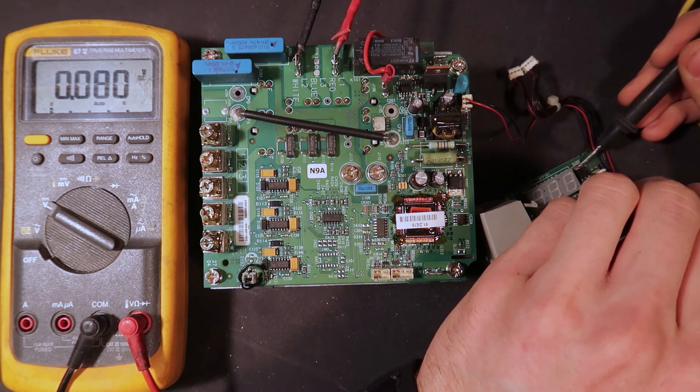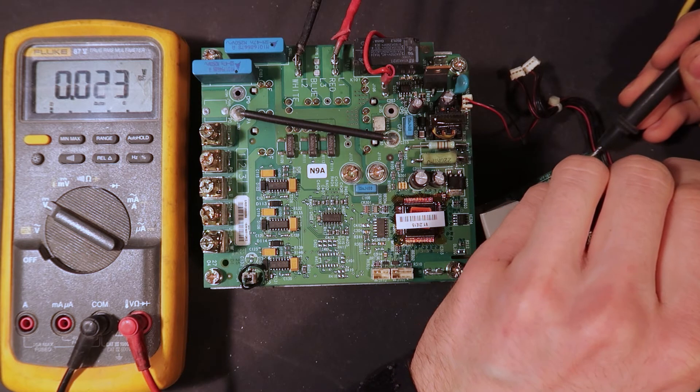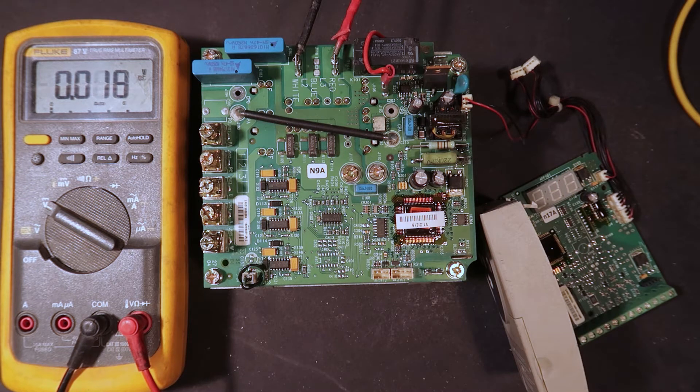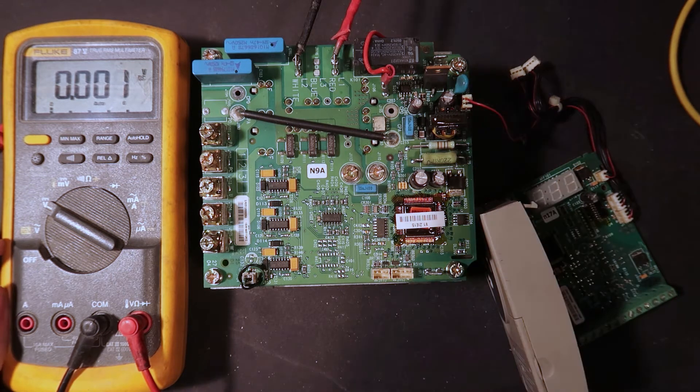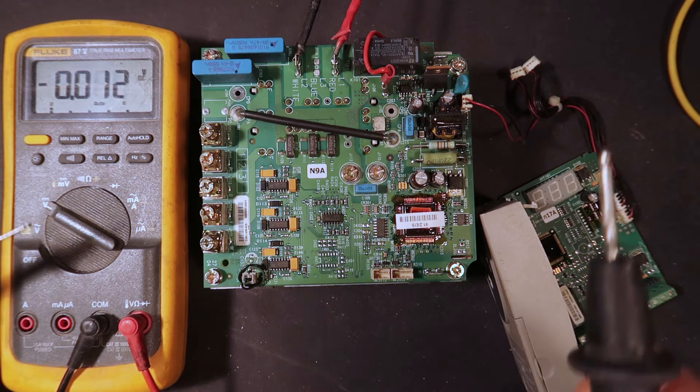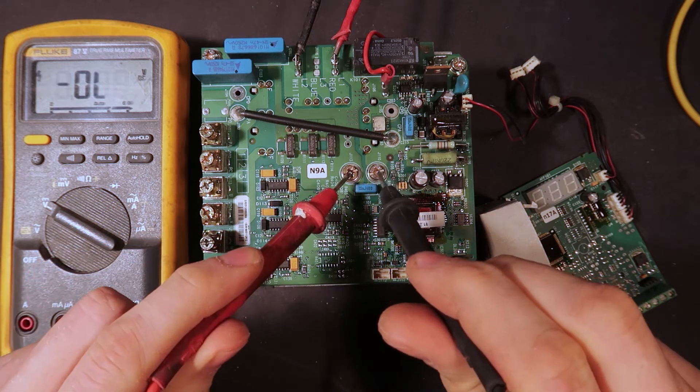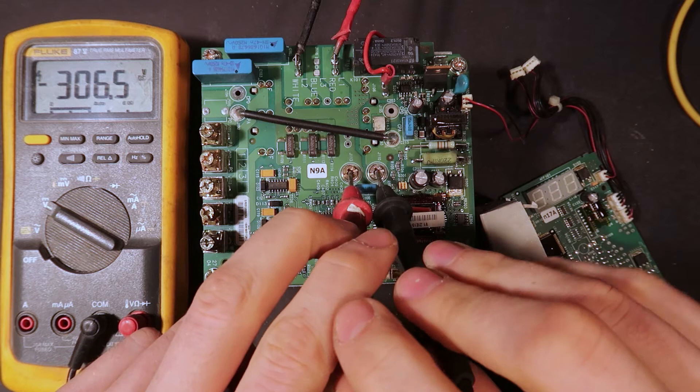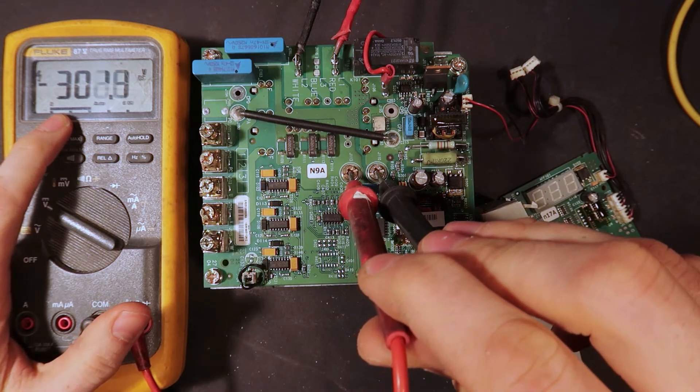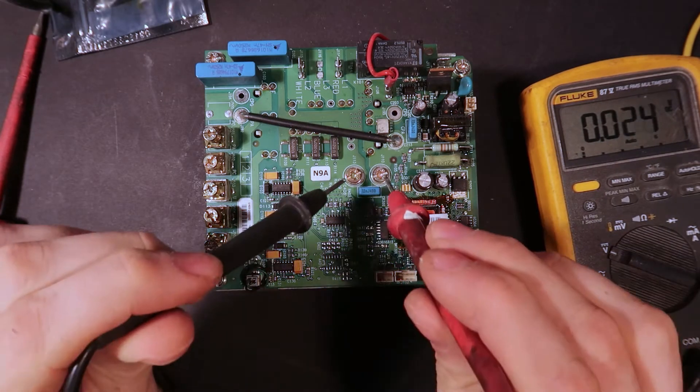And we can see there is a whole lot of nothing going on. Let's power this guy down. Be really careful by the way when you do this. Now I've removed the 240, but there's giant caps in here, and if we measure the DC bus, there is a discharge resistor on this but it's not very big. We still have 300 volts here and it's going to stay here for quite a bit of time. That has been about five minutes or so.